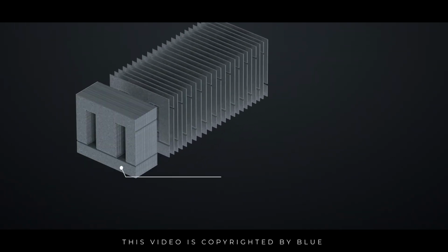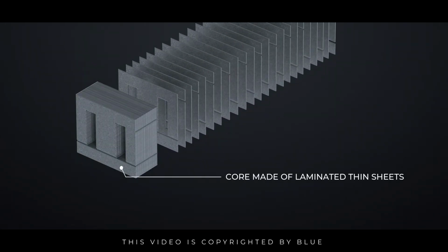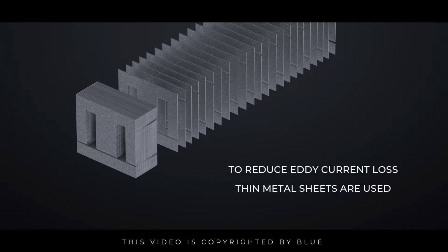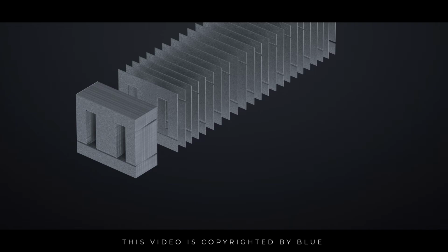The core which is used in a transformer is not a solid core. It is made of a number of thin sheets of metal, called laminations. This type of construction is used to reduce the eddy current loss which occurs inside the core. The core is used to provide a low reluctance path to the flux. These sheets are insulated by a very thin coating of insulating varnish or by the use of an oxide layer.